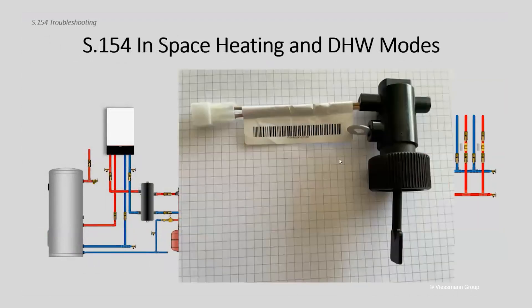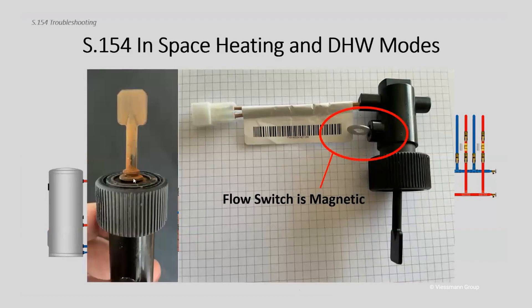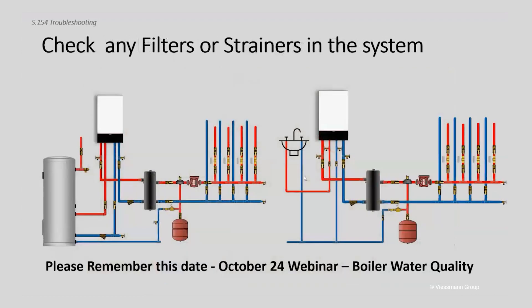I'd also recommend looking at the flow switch itself. Notice this little picture — I put a metal washer up against the paddle of the flow switch here. It's actually a magnet, not a spring, that pulls the paddle back to its default position after pump flow stops. This is magnetic. If you open up the flow switch, this one here came back for inspection and had a lot of buildup of debris on the paddle, which effectively stuck the flow switch in the open position. The flow wouldn't push the paddle closed anymore because it was all junked up.